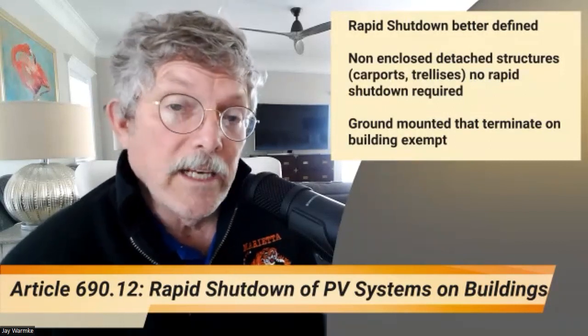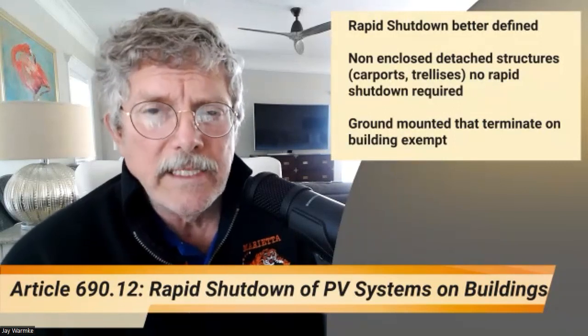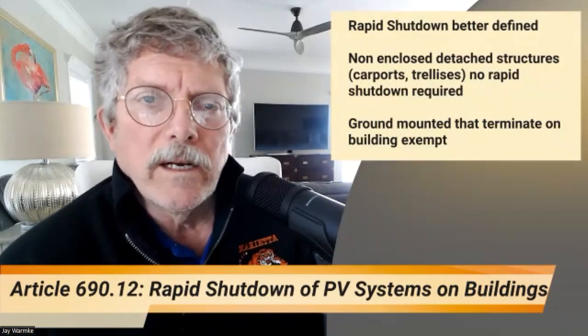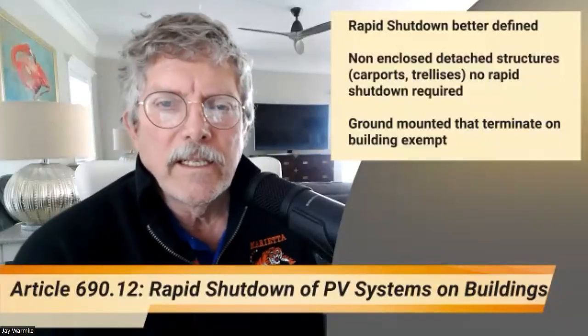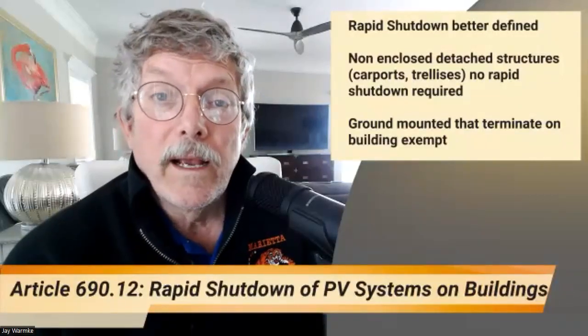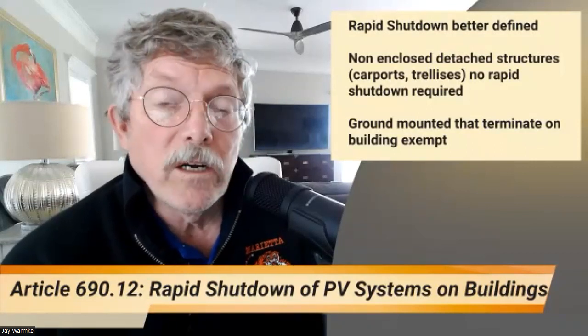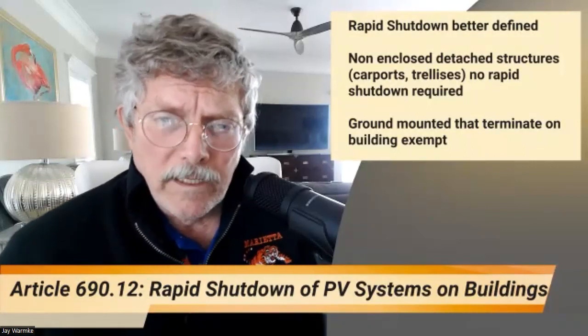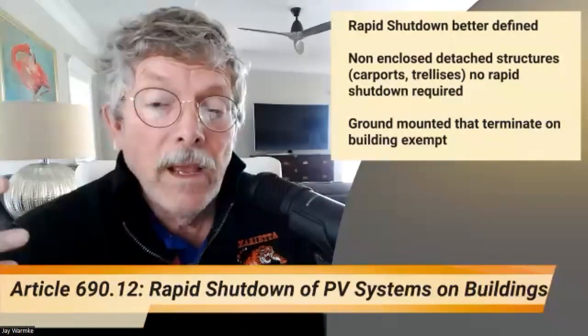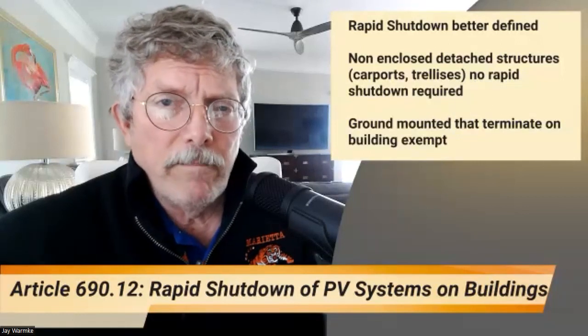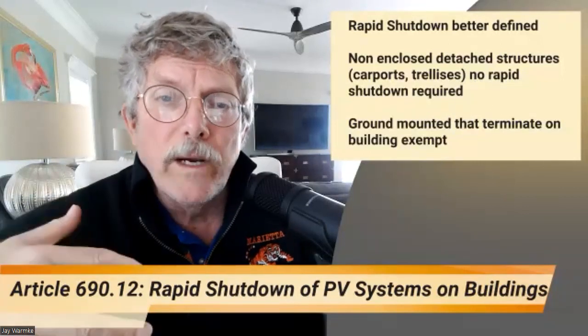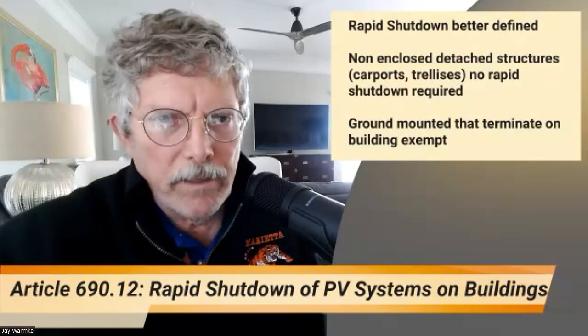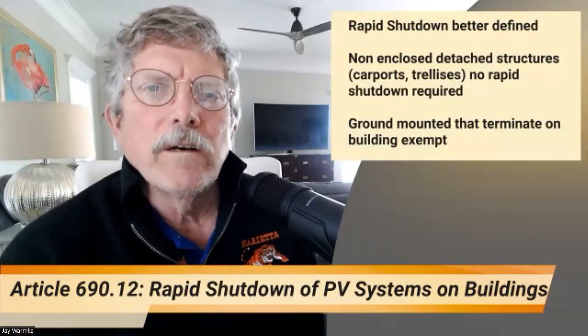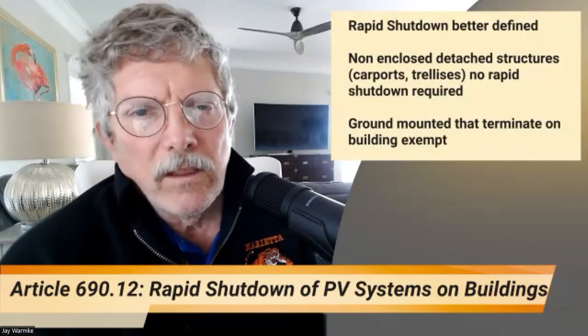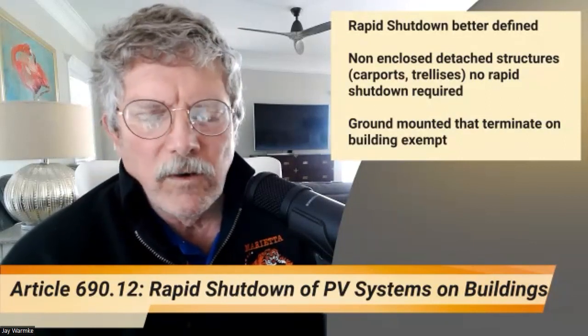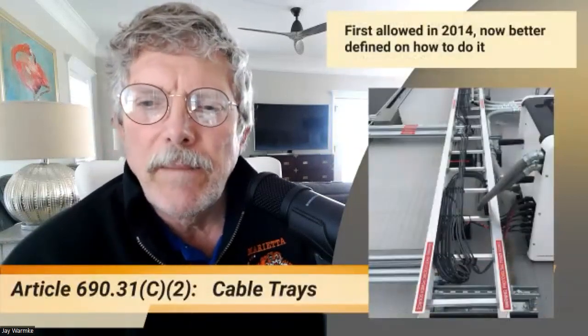So they're saying, okay, these electronic devices that you have to hook up to make this happen, the module level power electronics, are not required if you're installing it on a detached carport. Also, I guess there was some confusion, and it never occurred to me, that if I had a ground mounted system, well, ground mounted systems don't have to have rapid shutdown. But what happens if you bring those wires up to an occupied building and attach the inverter to the building? Well, they're saying, okay, in those situations, rapid shutdown's not required. So they're defining things a little bit better.